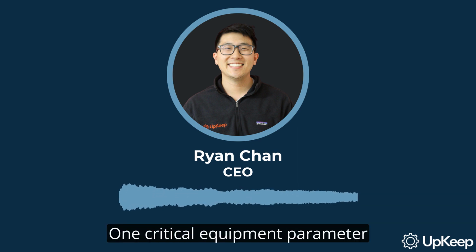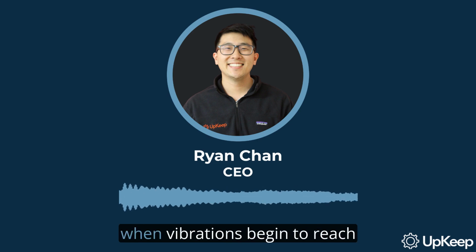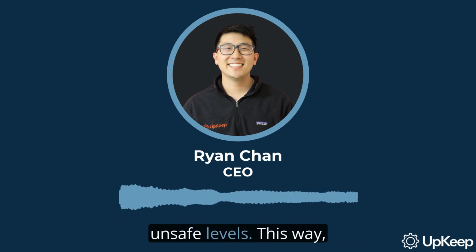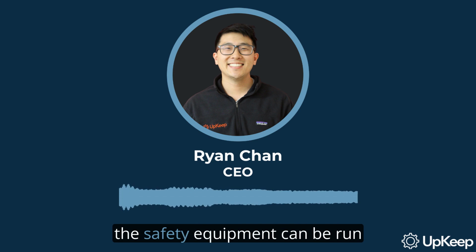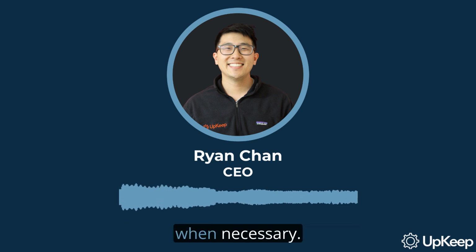On the other hand, let's say an organization needs to make sure that a critical piece of safety equipment can be maintained while it's running at load. One critical equipment parameter is the amount of vibration produced. The organization decides to implement CBM so that maintenance is performed only when vibrations begin to reach unsafe levels. This way, the safety equipment can be run constantly during maintenance and only receives maintenance when necessary.